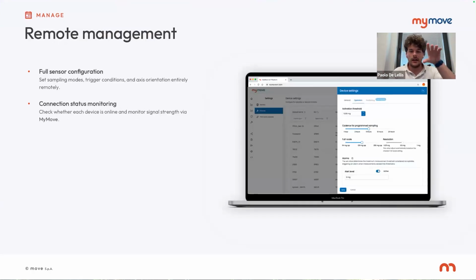But of course, our system allows you to configure all the sensors in different ways remotely. For example, one of the last features that we released for the new version of the sensor, for example for the tiltmeters, is the possibility to configure the axis remotely directly from your desk. And this is very important to make the installation phase easier for you.